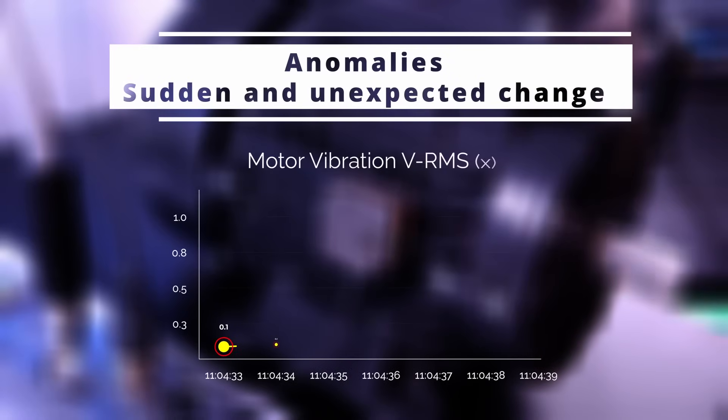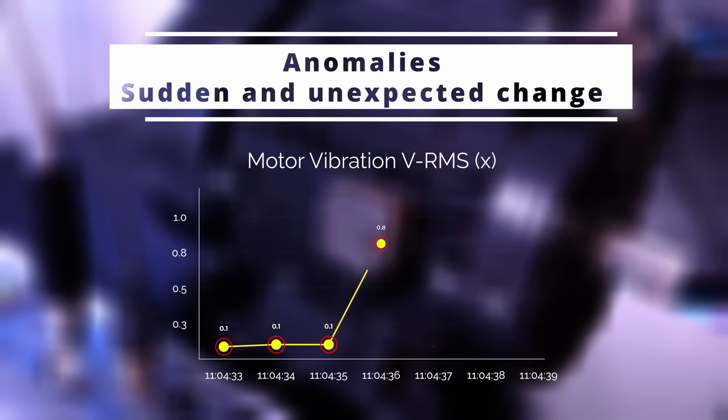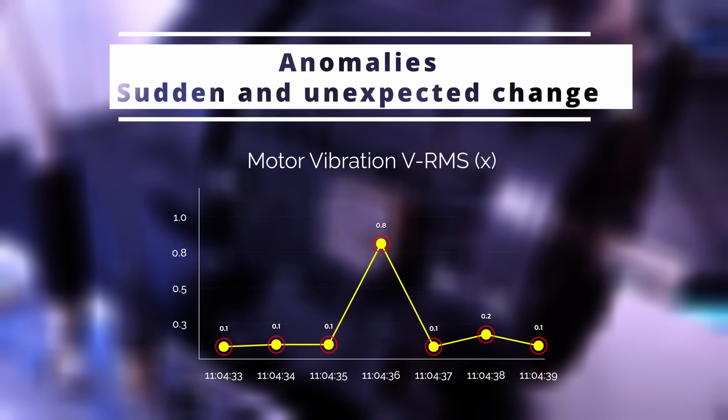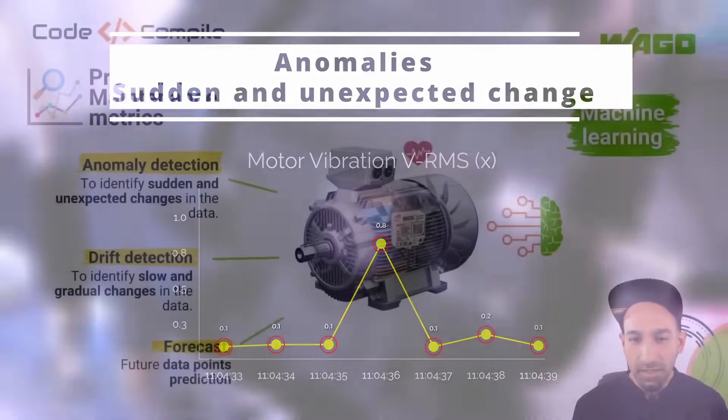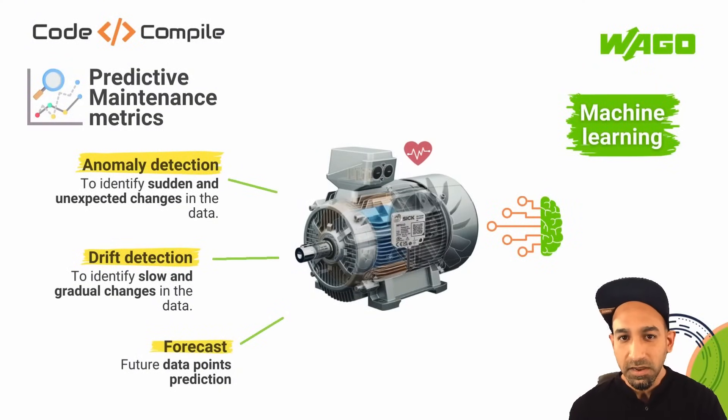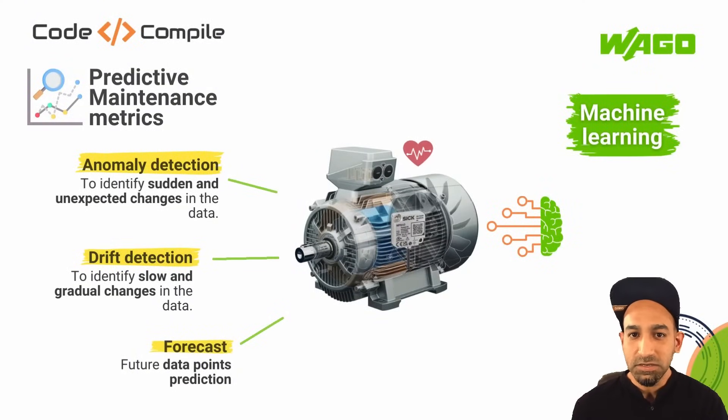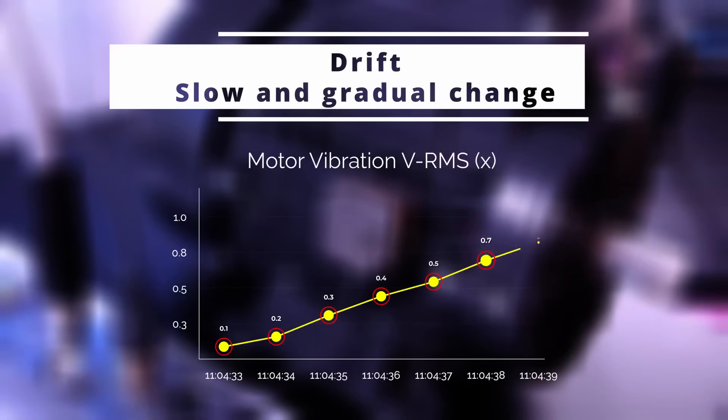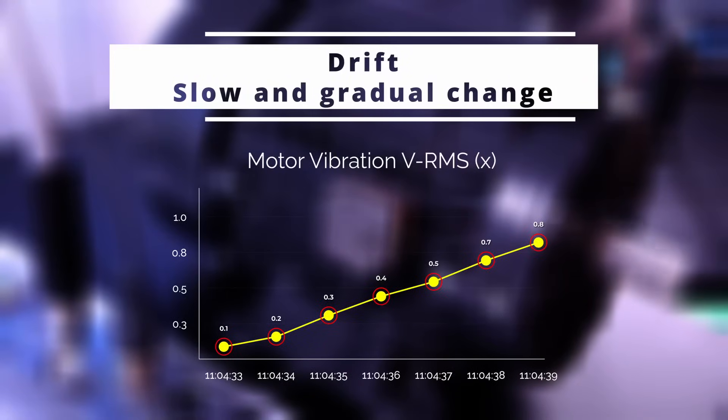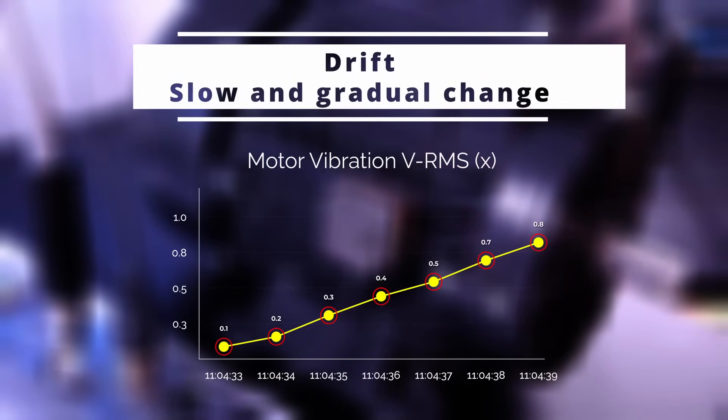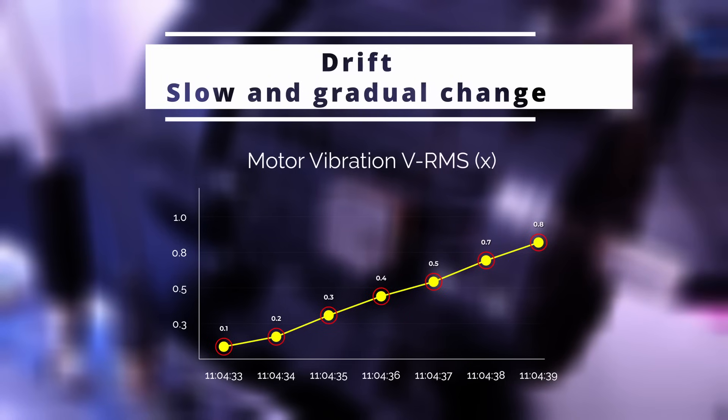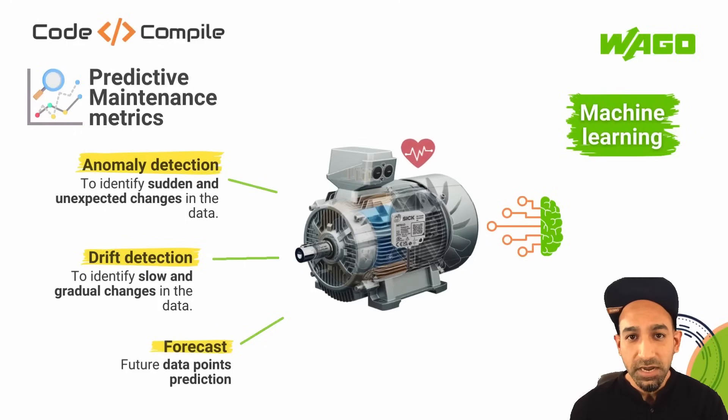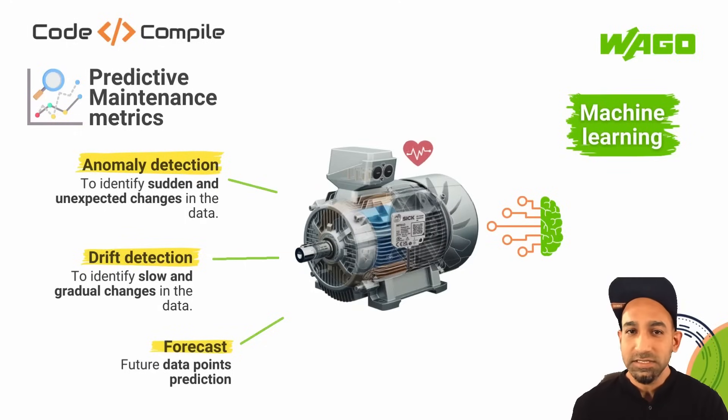The question is what is anomaly? Anomalies are sudden and unexpected changes in the system or change in the motor vibration data, which could be because of vibration spikes, bearing failure, imbalances, or some loose components. Whereas drifts are slow and gradual change in the motor vibration. Gradual change can also be because of wear and tear, slight misalignment, or just like aging of the component.